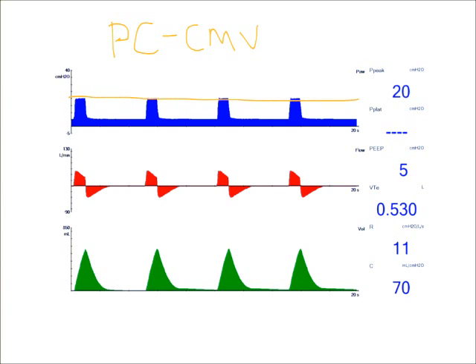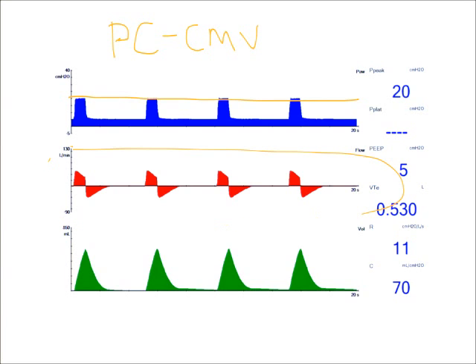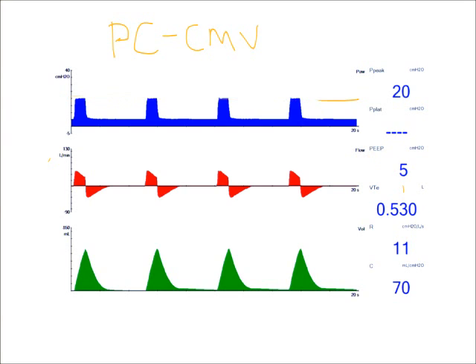where I have a constant pressure and then my flow varies. So how do I make sure that my inspiratory time is set correctly based on my waveform? I can look at my flow waveform.